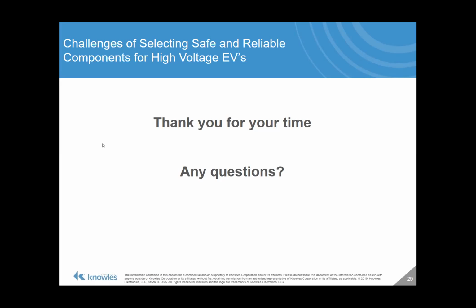Someone says you mentioned test voltage 4,000 volts DC for 800 volt DC battery systems. What are you seeing as working voltage isolation levels? I'm not quite sure on the question there. We are seeing that the requirement for board test is around 4,000 volts DC, and that is every time the board needs its test to be done. I'm not quite sure what you would refer to as working voltage isolation levels. My interpretation would be that it's always going to be tested at 4,000 volts DC, and then it will be working at 800 volts DC with a ripple on top.